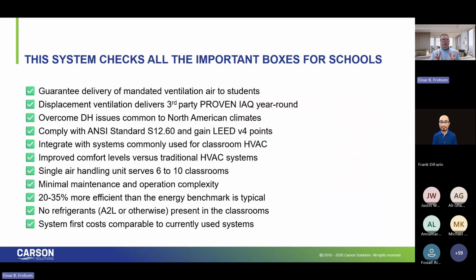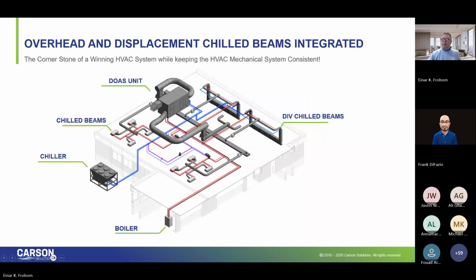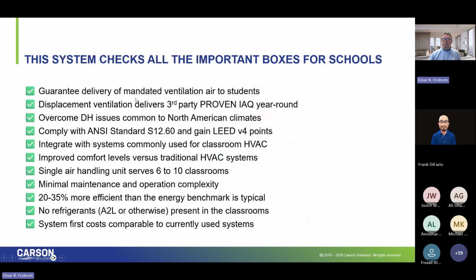The displacement induction ventilation device is the dumbest piece of equipment in this system. Same thing with the chill beam. These devices don't know anything better than to work. Feed it the right amount of outside air, feed it the chilled water, the hot water. It's just going to do its job. But applying the DOAS unit, that device helps ensure that we get the right amount of outside air, proven outside air, to these spaces. That's so important. Doing a better job of dehumidification makes the system more efficient, and it helps create a better thermal comfort environment.